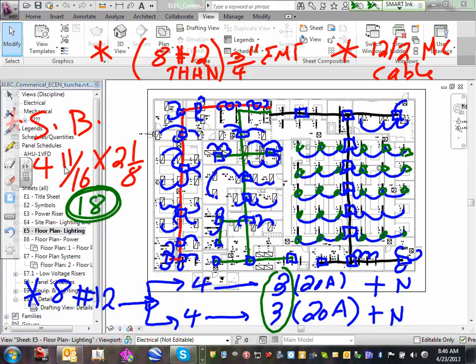Any comments, guys? I'm going to flip, if you don't mind, Jeff, using your project, into the receptacles and just draw a couple of things in the receptacles. Now I want to remind you guys, this ceiling is a 12-foot ceiling, so as you go down, make sure you accommodate for going 12 feet into the panel. Every time you go to the panel, if you account 10 feet going to the panel, that's great because the panels are high enough. So when you drop down here, at 10 feet going into the panel. Any comments, guys, about this conduit system?